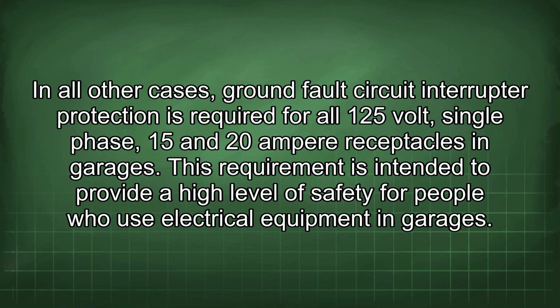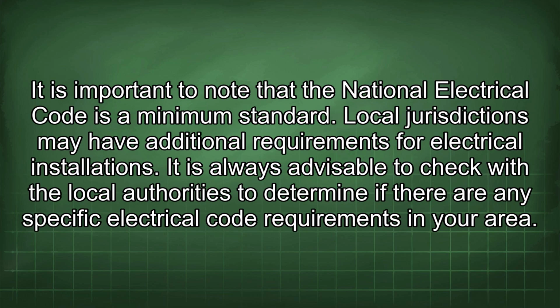In all other cases, ground fault circuit interrupter protection is required for all 125-volt, single-phase, 15 and 20 ampere receptacles in garages. This requirement is intended to provide a high level of safety for people who use electrical equipment in garages. It is important to note that the National Electrical Code is a minimum standard. Local jurisdictions may have additional requirements for electrical installations.